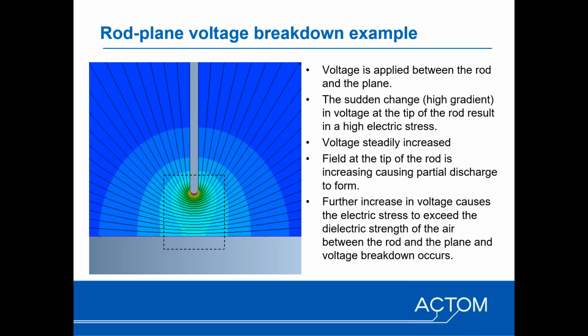Now, the breakdown phenomena can be explained by an example that we can look at. This is a typical rod plane scenario where you have an electrode in the form of a rod and an electrode in the form of a plane. Voltage is applied between the two electrodes, which gives a voltage distribution in the form of equipotential lines. Where there is a high concentration or gradient in the voltage, you get electric stresses appearing that are higher in those areas where the gradient is high. So when the voltage increases, the electric stress increases, and then partial discharge is formed. And if the voltage is increased to such a point where the electric stress in the gap between the rod and the plane exceeds the breakdown voltage of the medium in between, voltage discharge is formed.